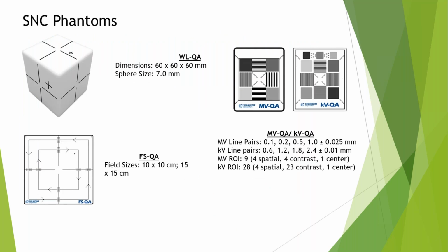Sun Nuclear has all the phantoms available that are needed for automated analysis, but it also supports other phantoms. Like in particular, I have the Leeds phantom and Catphan phantom, so they are supported as well. So if you have phantoms, you can check their compatibility list and see what you need. Otherwise, they have phantoms available if necessary.